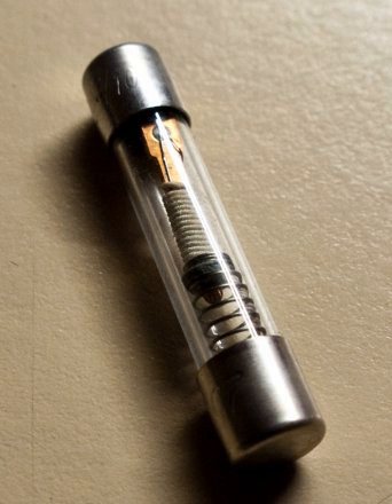The standard ampere ratings for fuses and circuit breakers in USA, Canada are considered 15, 20, 25, 30, 35, 40, 45, 50, 60, 70, 80, 90, 100, 110, 125, 150, 175, 200, 225, 250, 300, 350, 400, 450, 500, 600, 700, 800, 1000, 1200, 1600, 2000, 2500, 3000, 4000, 5000, and 6000 amperes. Additional standard ampere ratings for fuses are 1, 3, 6, 10, and 601.